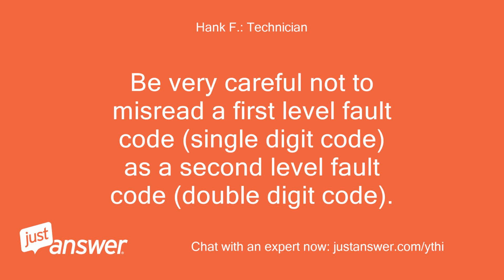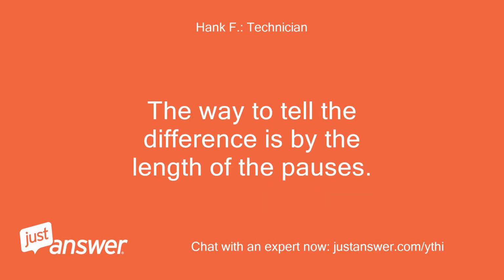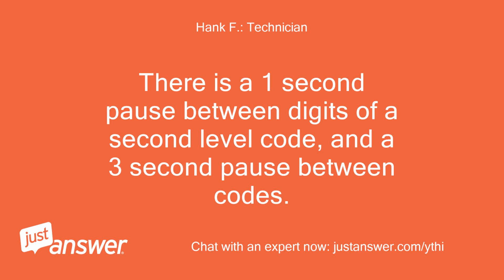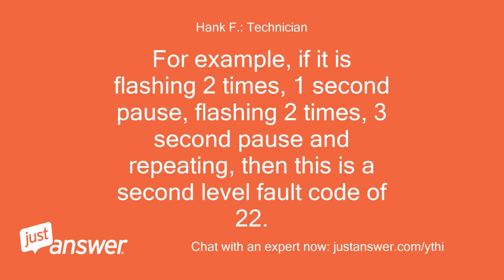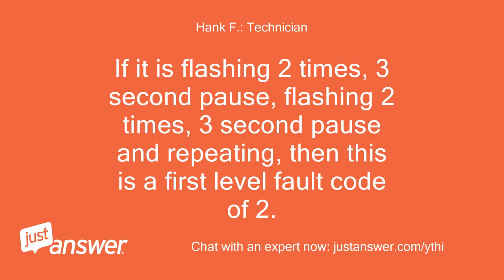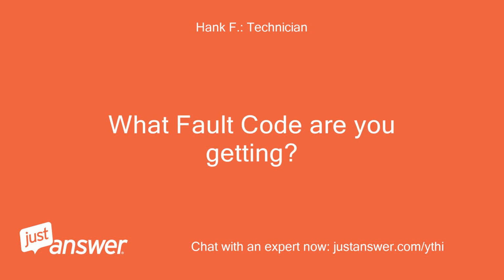Be very careful not to misread a first-level fault code, single-digit code, as a second-level fault code, double-digit code. The way to tell the difference is by the length of the pauses. There is a 1 second pause between digits of a second-level code, and a 3 seconds pause between codes. For example, if it is flashing 2 times, 1 second pause, flashing 2 times, 3 seconds pause and repeating, then this is a second-level fault code of 22. If it is flashing 2 times, 3 seconds pause, flashing 2 times, 3 seconds pause and repeating, then this is a first-level fault code of 2. What fault code are you getting?